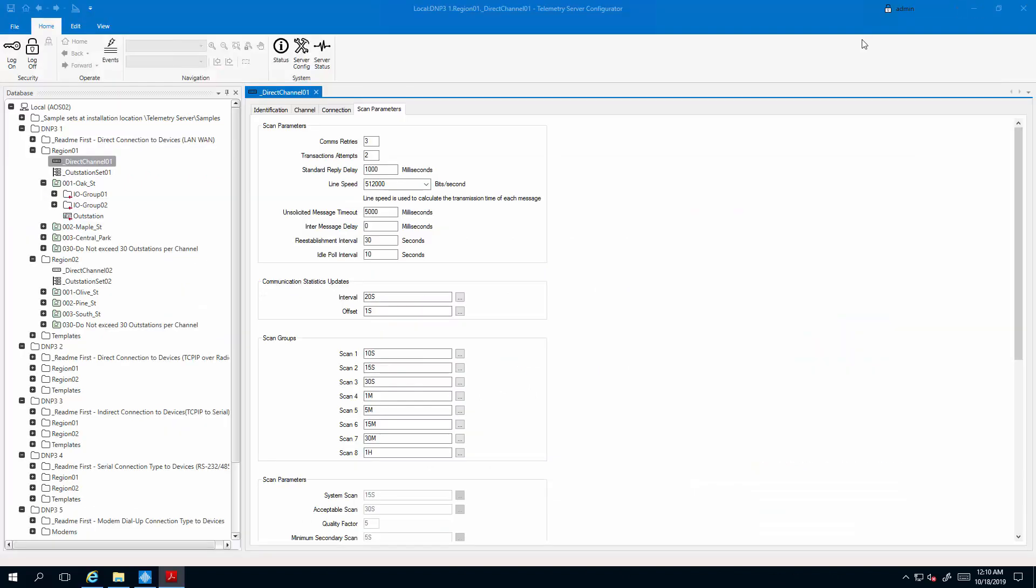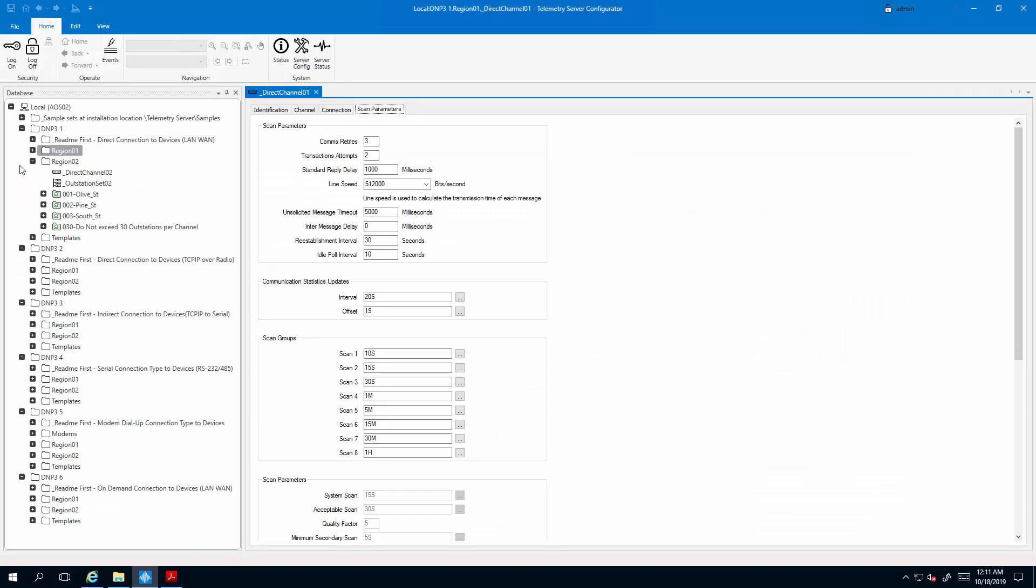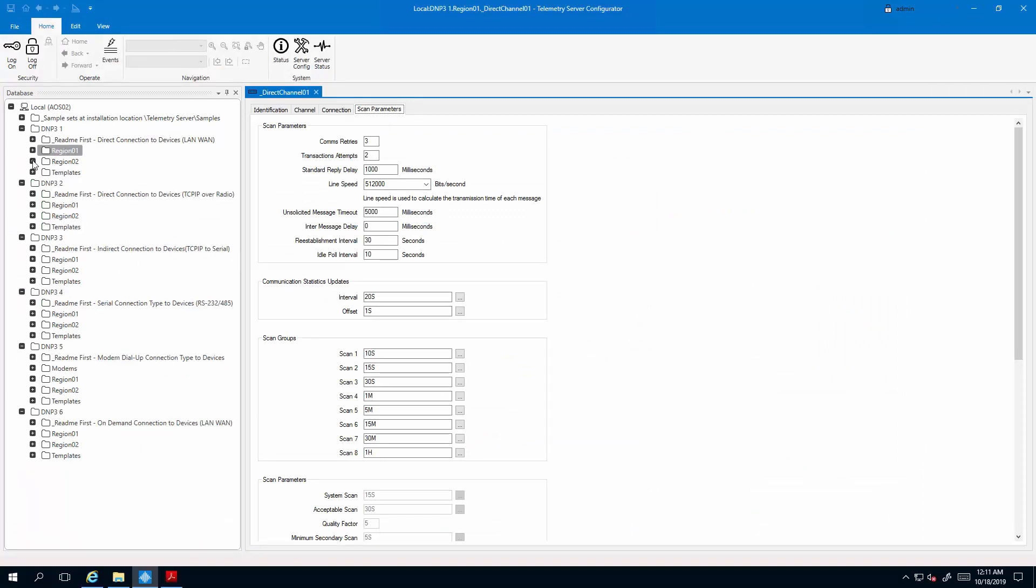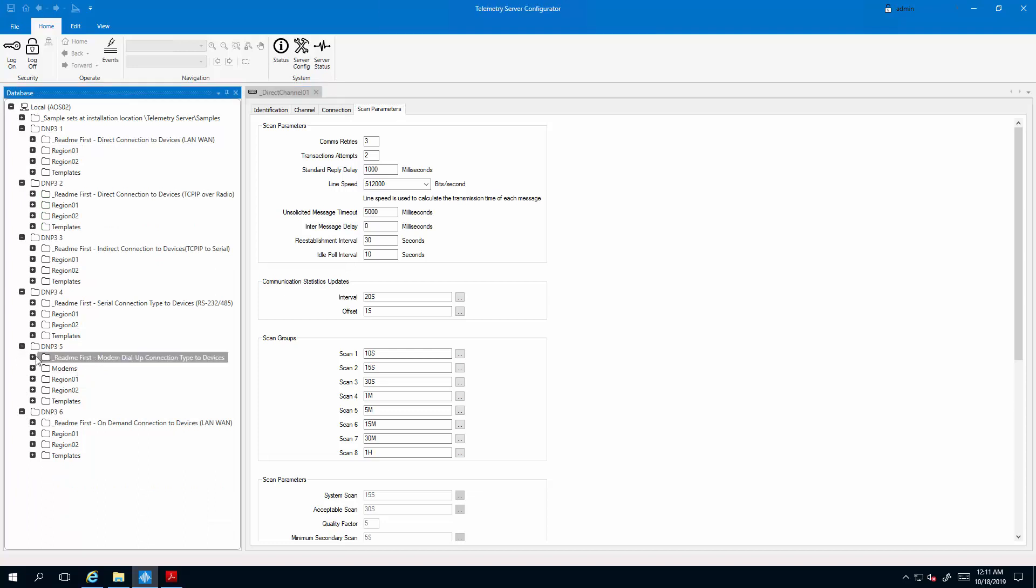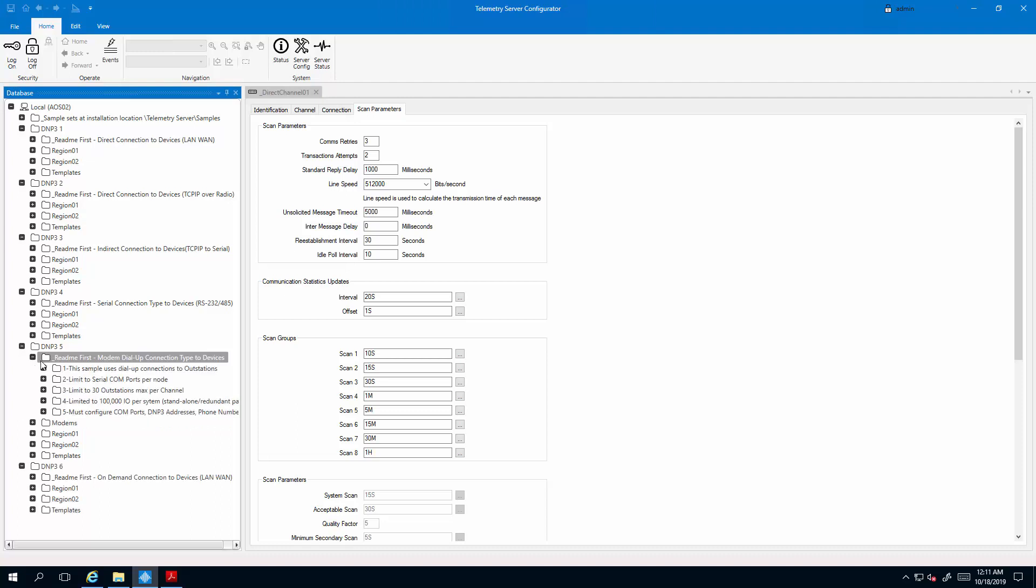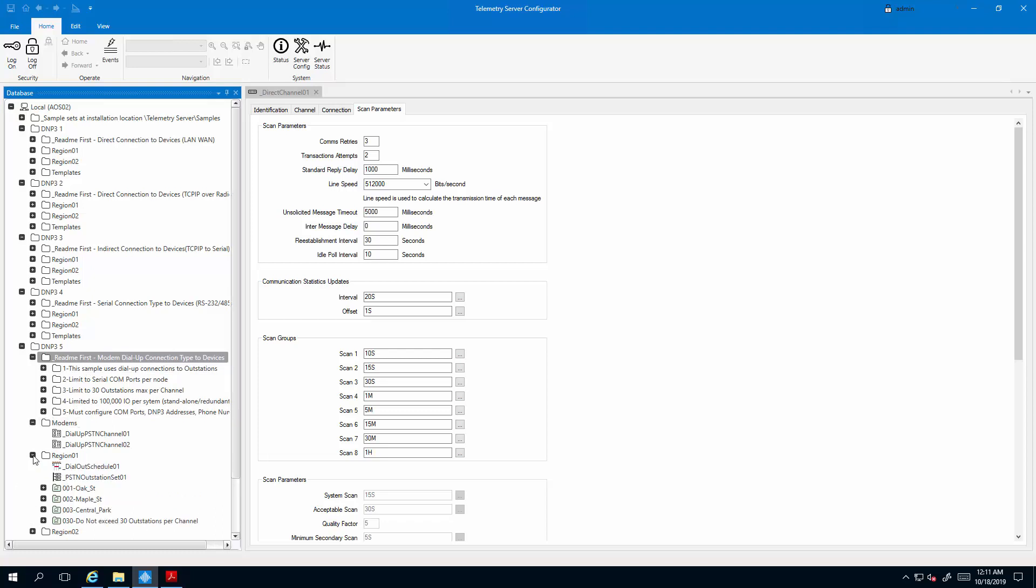Let me show that here in telemetry server just real quick. If I was to pick an on-demand connection to my devices, here are some of the details and the treatments. We actually have to add now modems as channels instead of our typical connection. And in addition, we have to consider how we are going to connect to those field devices. In the case of modems, we have to create a schedule, when to dial to the device and retrieve the data back.